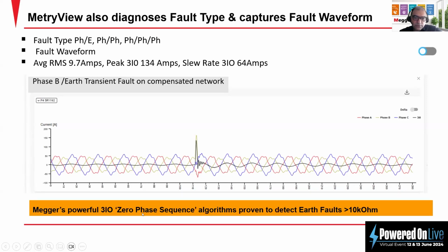And by the zero sequence fault algorithm, they can find this is a high impedance one, and they can find faults up to 10 kilo ohms. And as mentioned, it shows the average. For example, this one is 9.7 amps, peak is 134 amps, and slew rate is 64 amps. And all this information will be recorded in a data table of the fault.